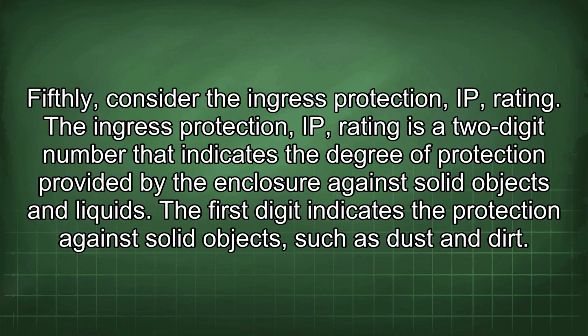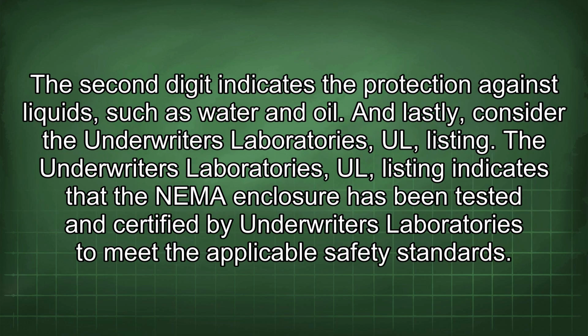Fifthly, consider the ingress protection IP rating. The ingress protection IP rating is a two-digit number that indicates the degree of protection provided by the enclosure against solid objects and liquids. The first digit indicates the protection against solid objects, such as dust and dirt. The second digit indicates the protection against liquids, such as water and oil.